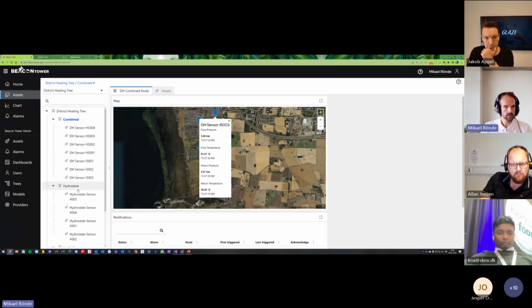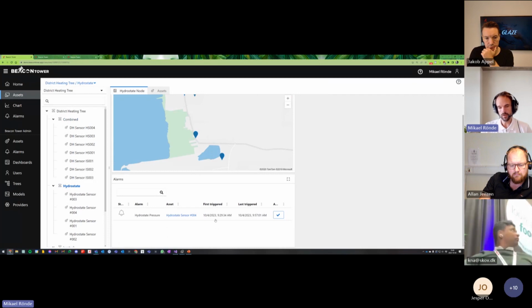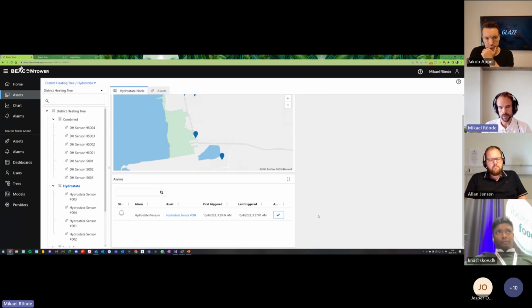The last thing we can cover here is a couple of different capabilities you have. For example, in Beacon Tower we can manage alarms—basically, when a telemetry value is outside of a certain threshold, we get an alarm here. Sometimes you choose to manage that outside in other systems, so we only send all our telemetry data out, and sometimes you want to handle it here to get an indication of something being wrong. It depends on the setup and what other systems you have around it.